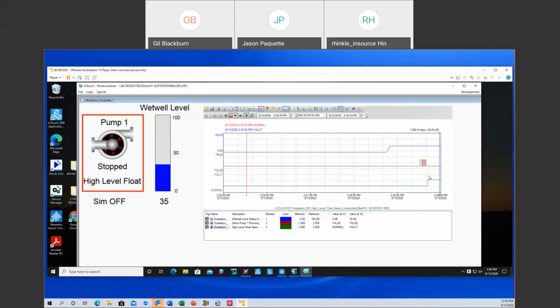So while we're not polling right now, I'm going to run the level all the way up, which is the top line, by the way. This is the pump, and here's my fault condition. And I'm going to run it all the way back down. Now, if I just waited 5 minutes, it would actually backfill. It just backfilled back in, I happened to catch it right. So I'm going to run that up, run that down.